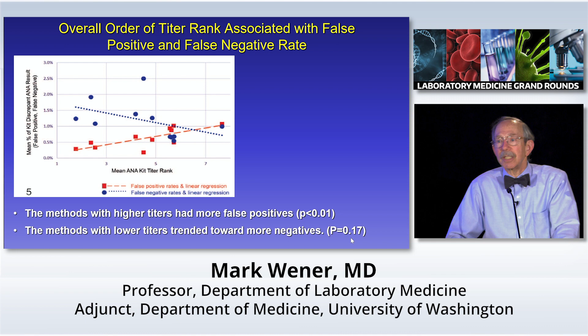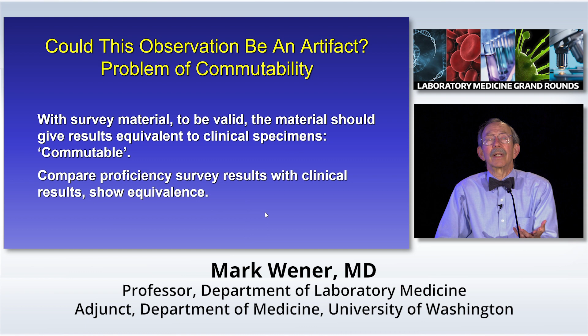One of the questions is, is this just an artifact? Proficiency survey material always needs to be stabilized and aliquoted and handled differently. So this is a problem of what's called commutability. The idea is that a survey specimen, or for that matter, a calibrator or a standard, to be valid, should give equivalent results as clinical specimens done with the same method in the same lab, and that is termed commutability. So in order to assess that, one would have to look at the proficiency survey results and then compare them with clinical results to show equivalence.